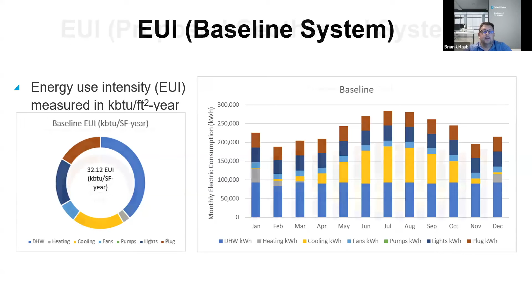When we added geothermal to this project, since in Florida there's not a lot of heat, it's mostly cooling, and the ground is still relatively warm - our ground temperature was 78 degrees - you only get a delta T between air and ground through the summer months of maybe 15 to 20 degrees, and that's where you gain your efficiency. So in Florida your EUI and efficiency doesn't dramatically decrease with geothermal, simply because of the ground and air temperatures and the fact that you don't have a lot of heating hours.